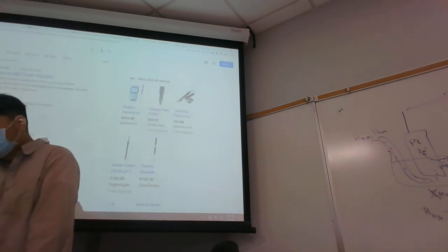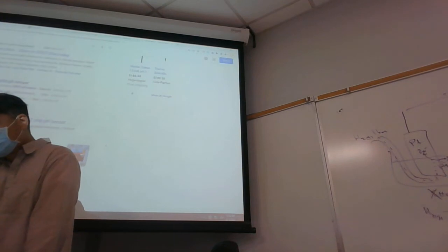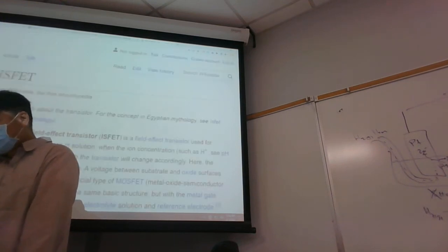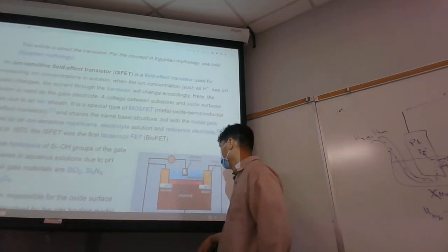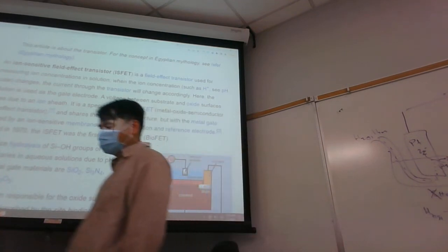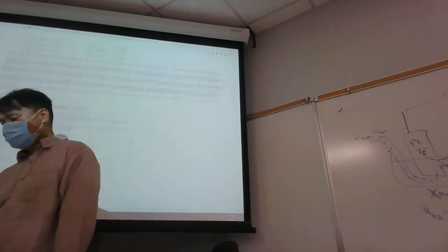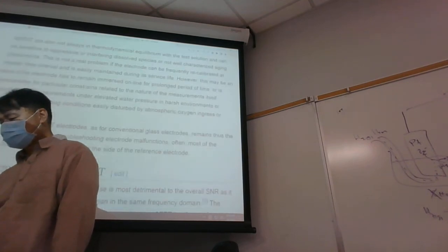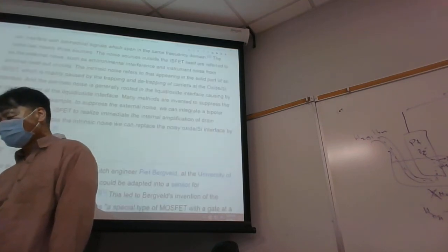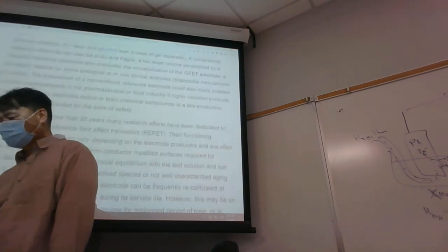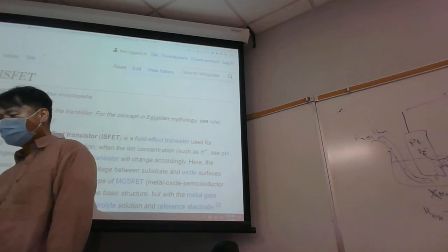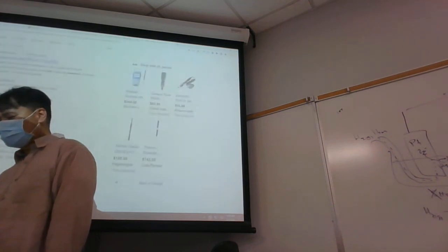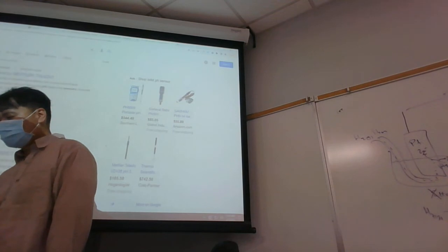Which looks like this: an ion sensitive field effect transistor pH meter. These have pretty rapid response and they're really robust. You don't have to condition them in solution. You can let them dry out, it's not a problem. You can measure semi-solids. You don't have to have much sample either, just a drop. And so these are much better, and the cost of these is coming down.